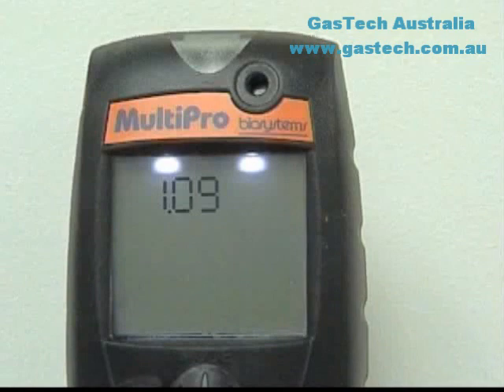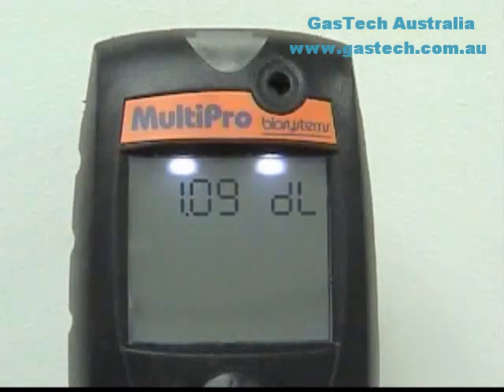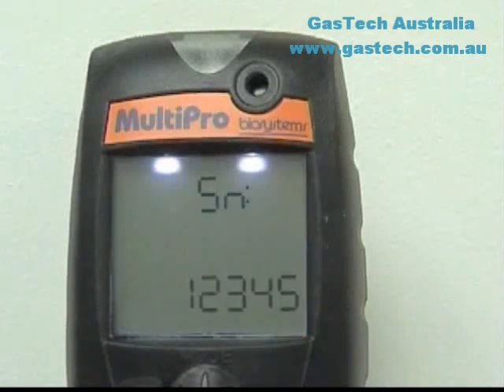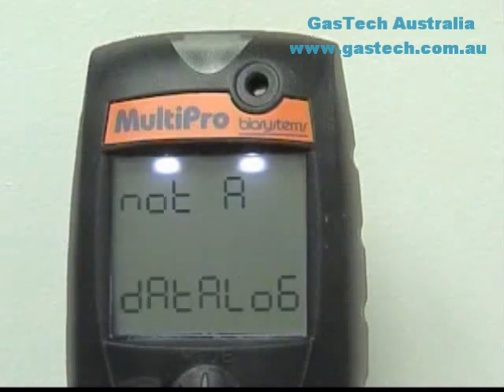The software version is shown next. If the instrument includes a fully enabled data logger, the letters DL will be shown to the right of the software version. The sensors recognized by the instrument will then be shown, followed by the instrument serial number. The Multipro includes a black box recorder as a standard feature. For instruments with the standard black box recorder, the screen will then display "Not a data log." This means the instrument does not have the data logging option enabled, but does still contain the black box recorder as a standard feature.